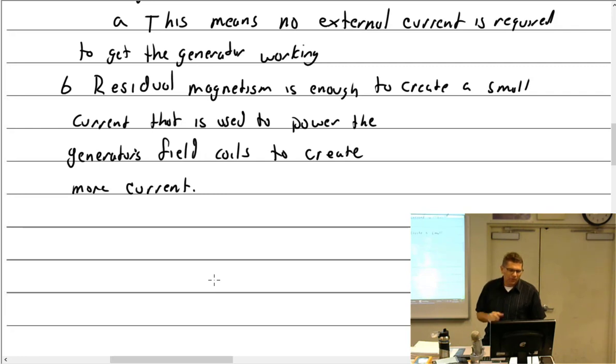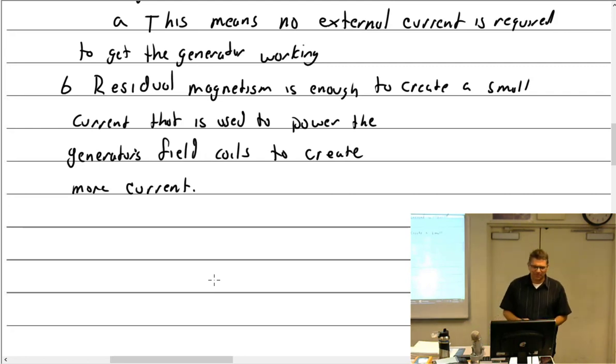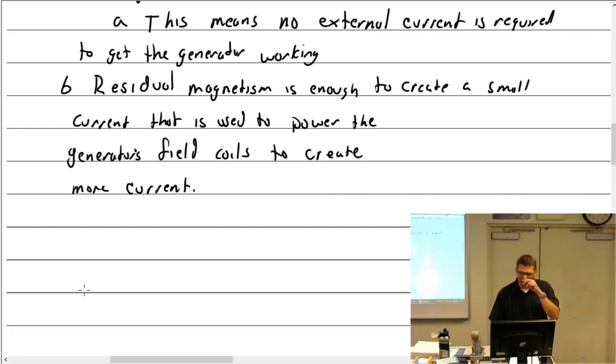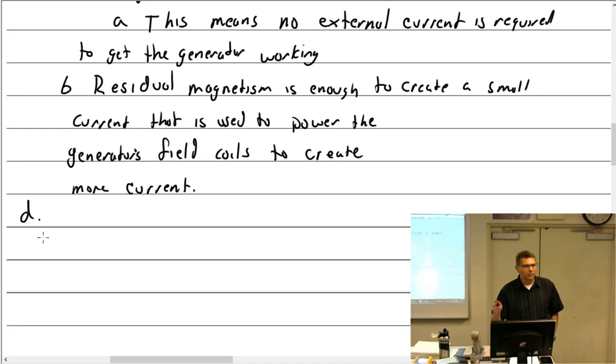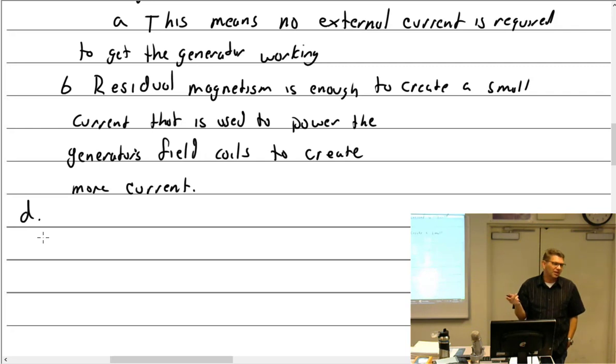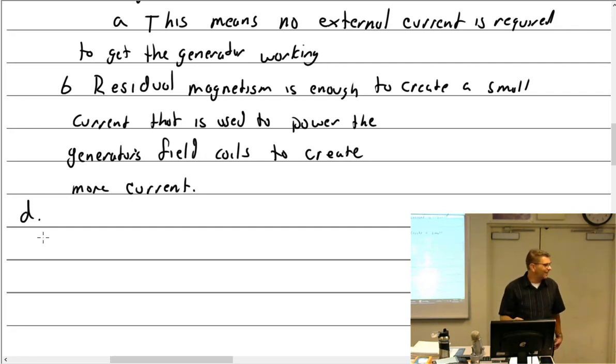What happens if you lose your residual magnetism — will the generator work? No. If you lose residual magnetism, or if it gets inverted so north becomes south and south becomes north, the generator won't work, and you have to flash it to get it excited again.